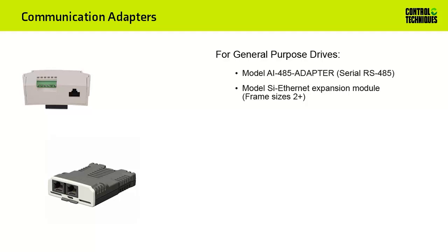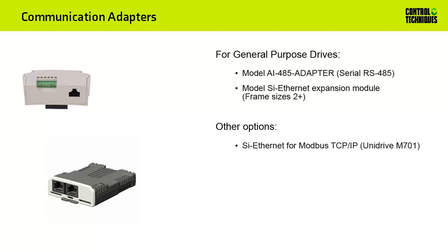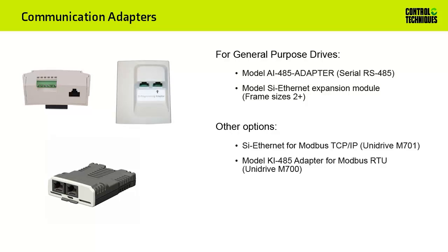The Unidrive M400 will require either the AI-485 adapter or the SI Ethernet module, depending on the type of Modbus communication desired. You may also add a SI Ethernet module to a Unidrive M701 to provide Modbus TCP-IP communication. A Unidrive M700 may also communicate using Modbus RTU by adding a KI-485 adapter.